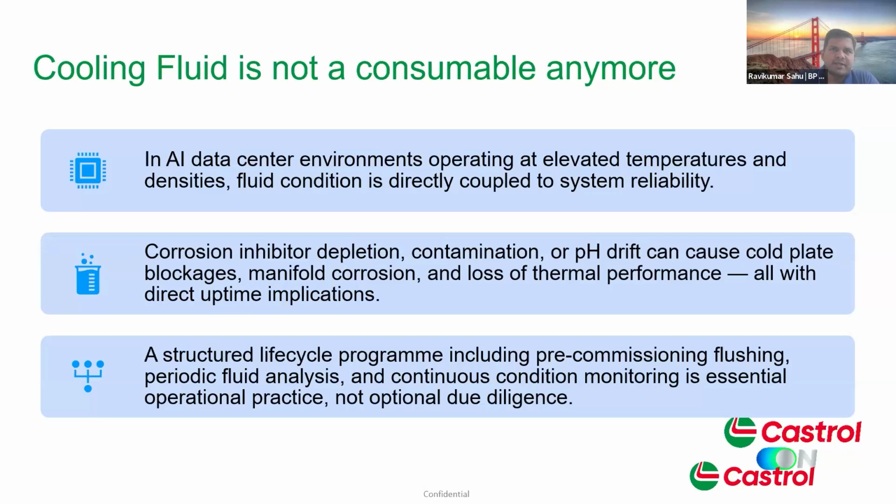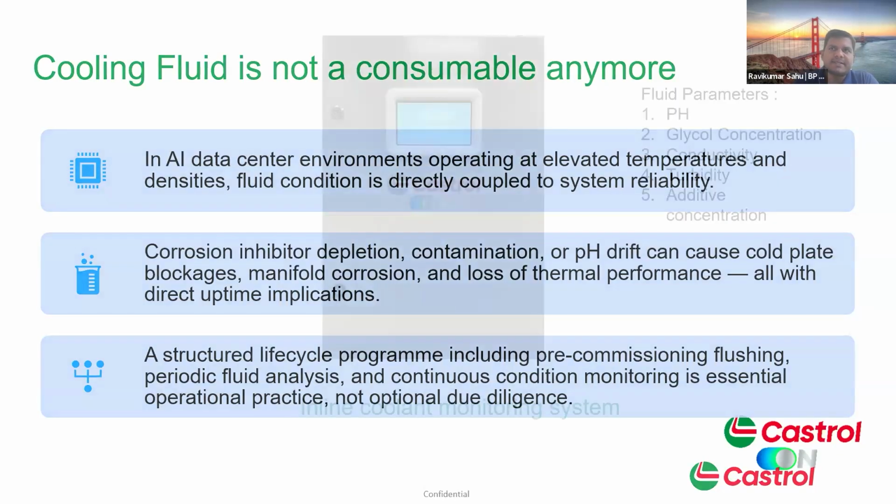Over time, your glycol concentration is depleting, which we need to take care of. And microbial growth is also a possibility. These are the things we have to keep in check all the time for smooth operations. So what we have is fluid monitoring sensors, because the fluid monitoring parameters should be at the level defined as per the standards.